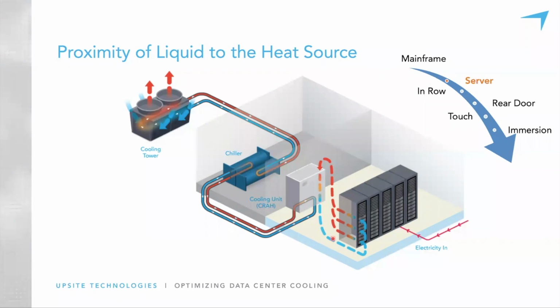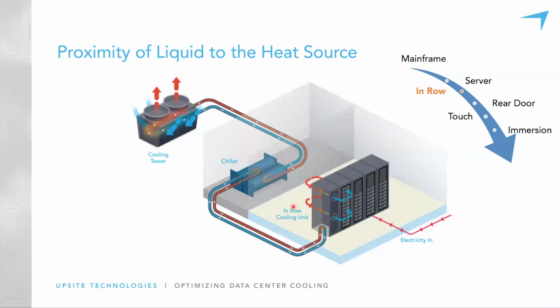So moving on to the in-row cooling, instead of having the cooling at the perimeter of the room, we move the cooling closer to the load. Now we have cooling units. Basically, it's a small cooling unit sitting in the row of the cabinets. And we're just showing one loop of air here, but of course, the air that's coming out of this cooling unit is going and serving all the IT equipment in this row. And it's the air that's the loop that picks up the heat, brings the heat back to a cooling unit where a heat exchange process occurs to pass the heat to the liquid. And then the liquid carries it out of the building once again. So we've moved the liquid a little closer to the heat source in this case.